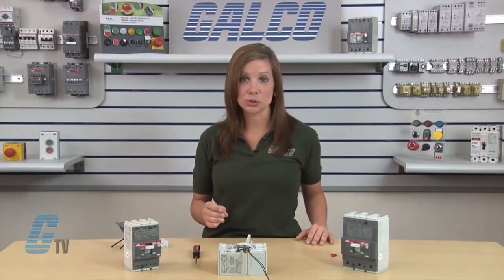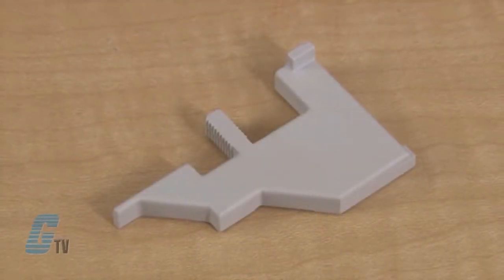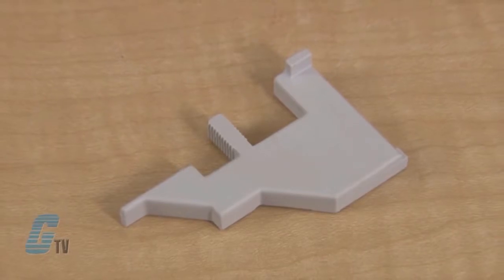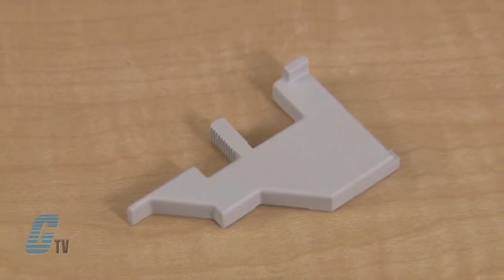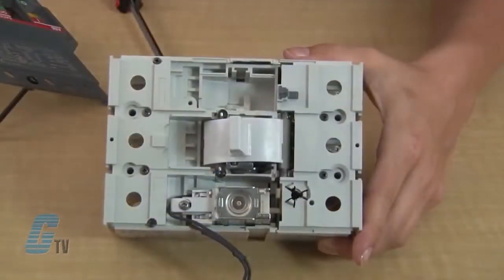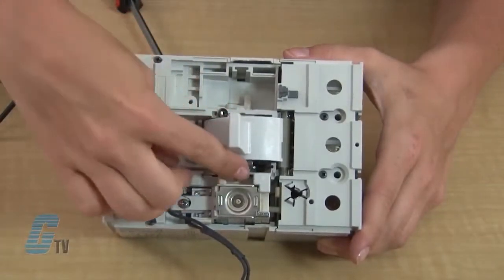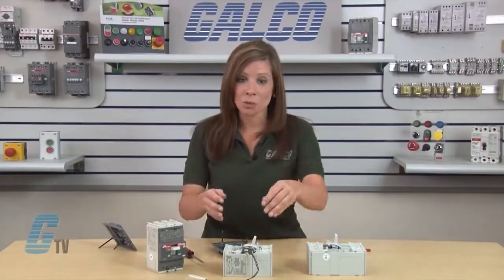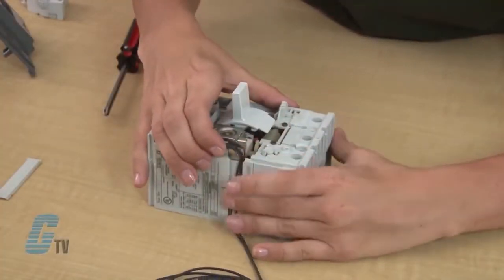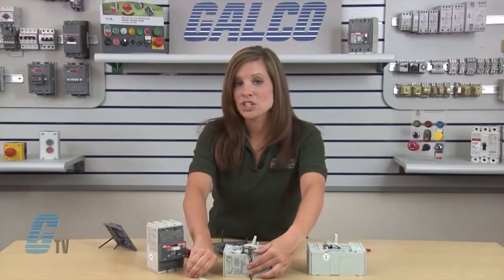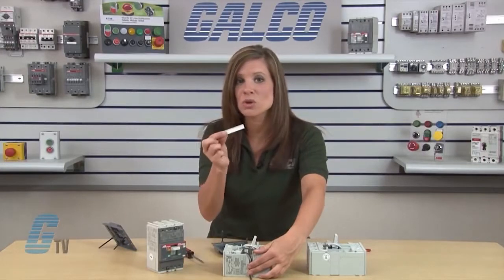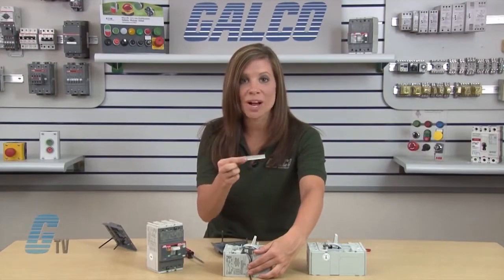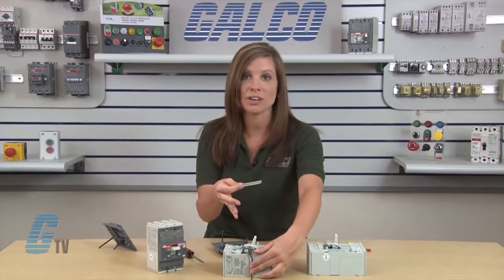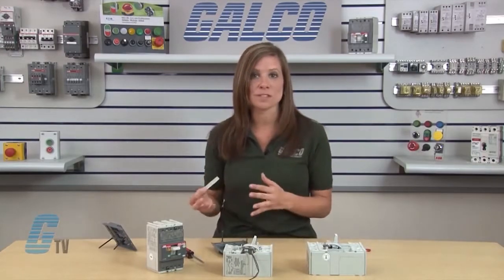A step that is exclusive to the T3 model is the installation of this spacer, which is not required on the T1 or T2 models. I will insert this spacer to the right of the UVR unit. The wires should be routed along the wire channel on the outside of the circuit breaker frame. The wire channel cover can be shortened so that the wires can exit the channel right at the surface of my enclosure panel when the circuit breaker is surface mounted.